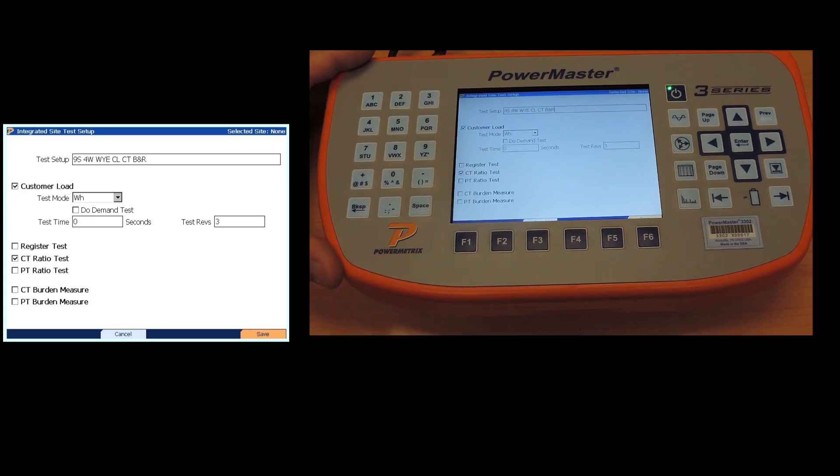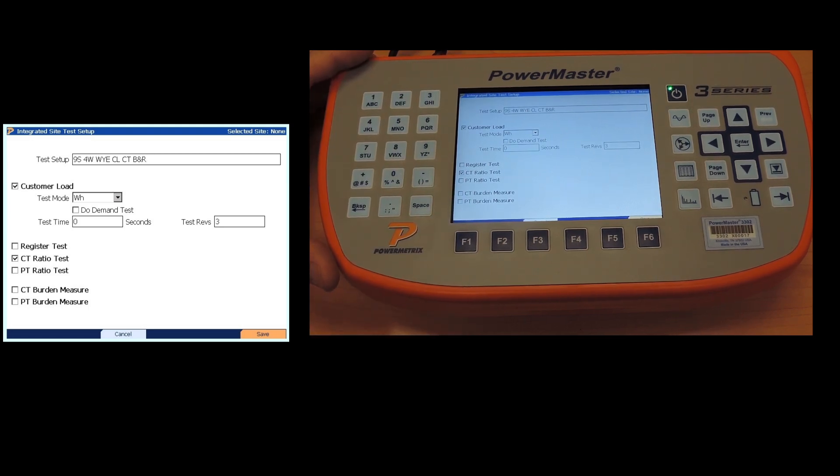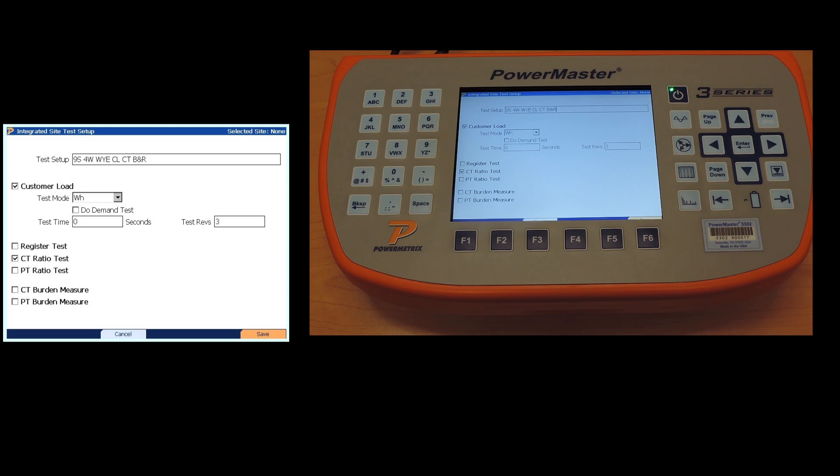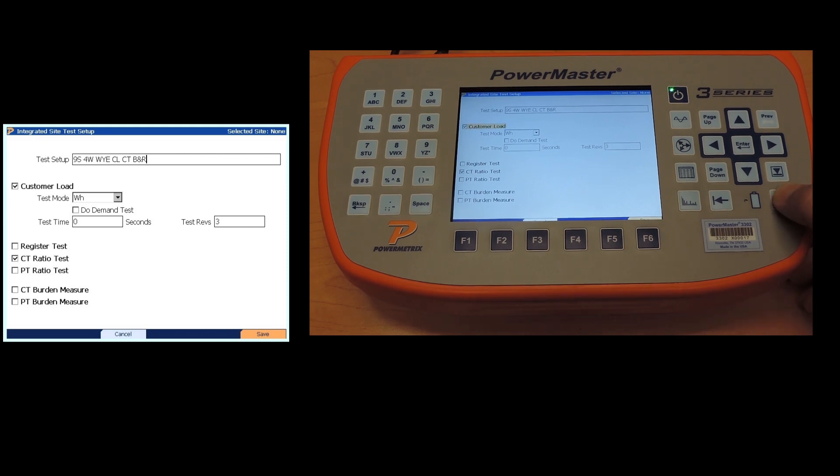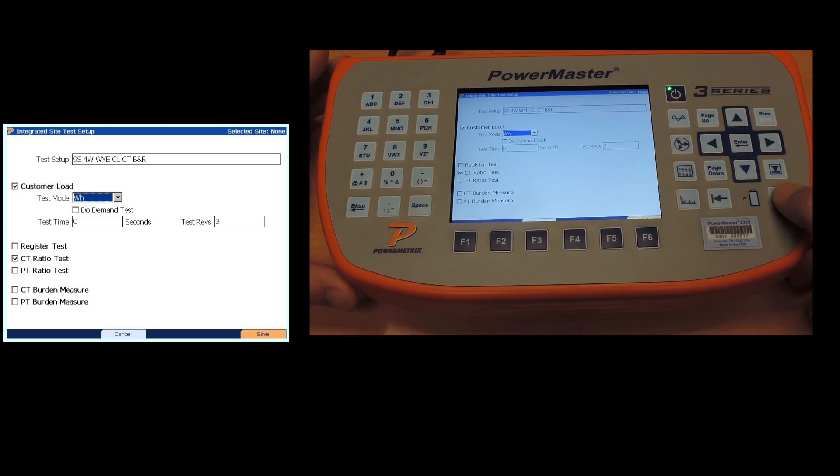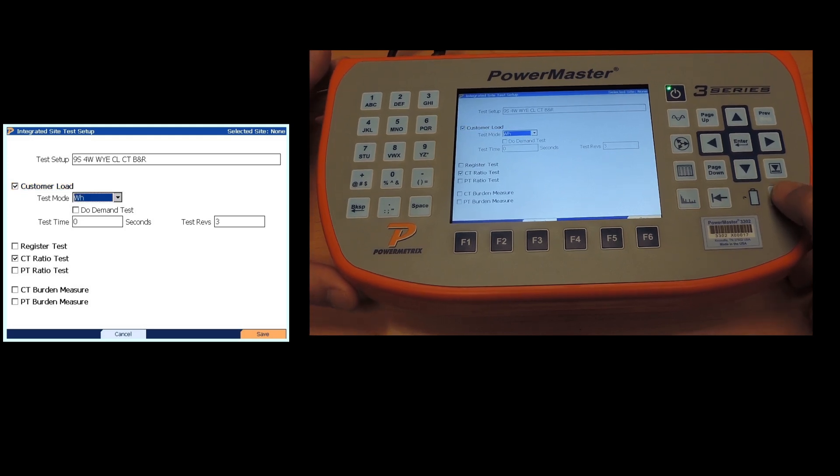By selecting the name this way, anytime I'm doing a form 9S meter, it's a four wire Y, I just have to select this test menu. I don't have to go in and recreate it. We're doing a customer load, we'll be doing it in watt hours. If we want to do a demand test we would check that box.